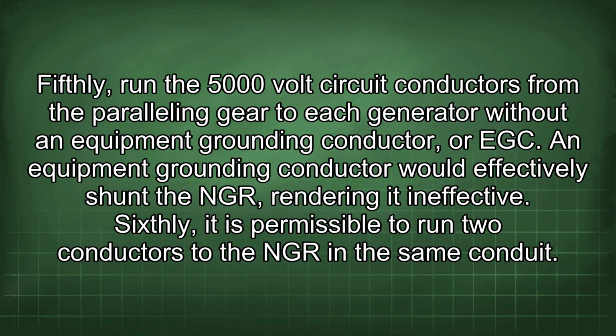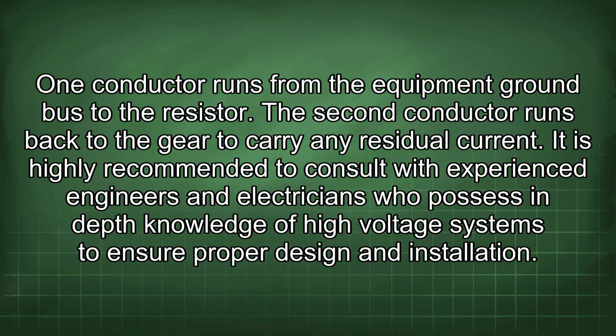Fifthly, run the 5000 volt circuit conductors from the paralleling gear to each generator without an equipment grounding conductor, or EGC. An equipment grounding conductor would effectively shunt the NGR, rendering it ineffective. Sixthly, it is permissible to run two conductors to the NGR in the same conduit. One conductor runs from the equipment ground bus to the resistor. The second conductor runs back to the gear to carry any residual current.